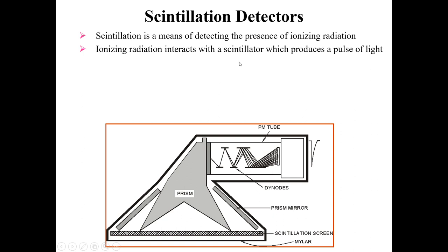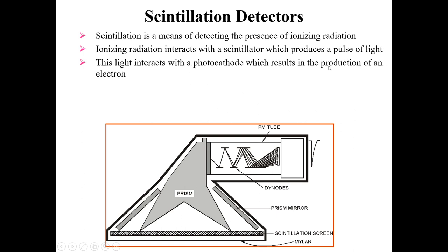When the ionizing radiation interacts with the scintillator, it produces a pulse of light. This initial light, produced by the interaction of ionizing radiations with the scintillator element or compound, then interacts with the photocathode.